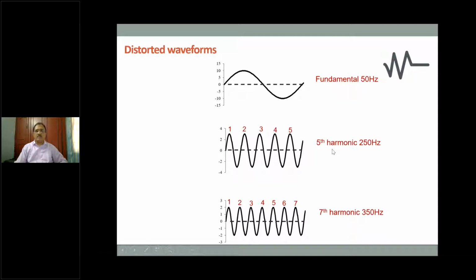Typically, even order harmonics cancel themselves. So you will not find, after the fundamental being 1, the 2, 4, 6, 8 order harmonics, as they will be cancelled, and you will not find them in any of the equipment that you use to measure the harmonics. So you will always find the odd order harmonics: 1, 3, 5, 7, 9, 11. These are the numbers which you will typically see in a wave shape.